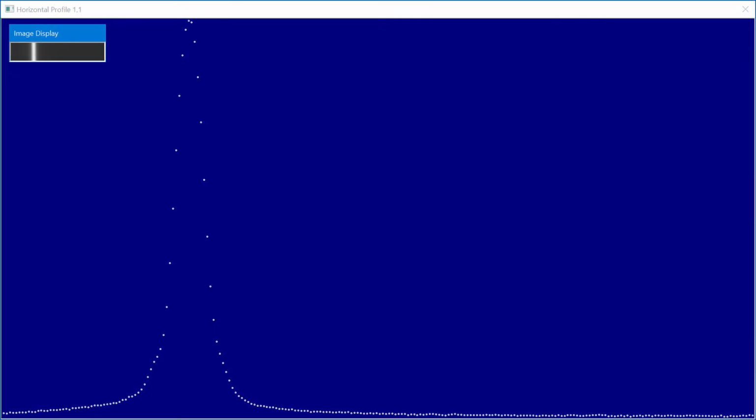To the eye, the motion looks fine, but how accurate is it really? And how does operating the piezo in open and closed loop affect its performance? We can answer such questions simply by tracking and analyzing the motion of the microscale. To simplify tracking, we define a small region of interest that contains only a single bright bar. The vertically averaged horizontal intensity profile of this region contains a strong peak that corresponds to this bar.